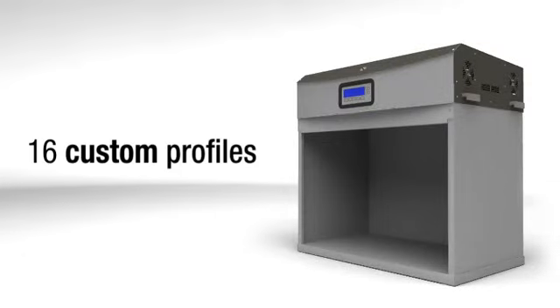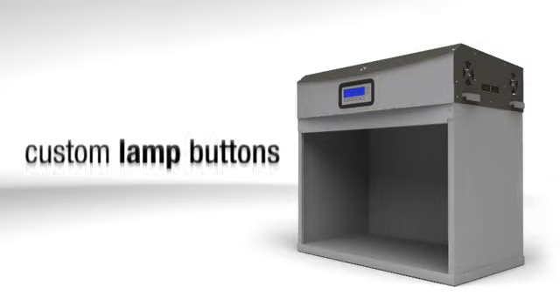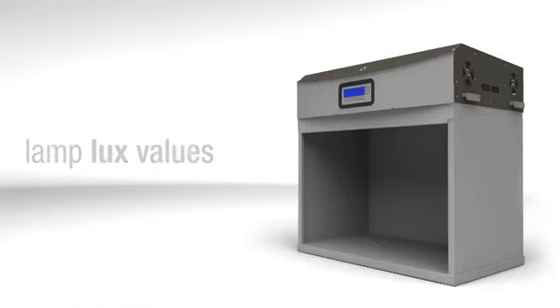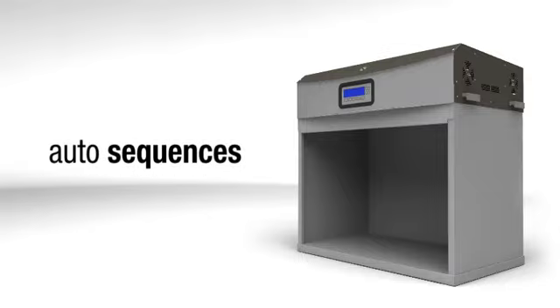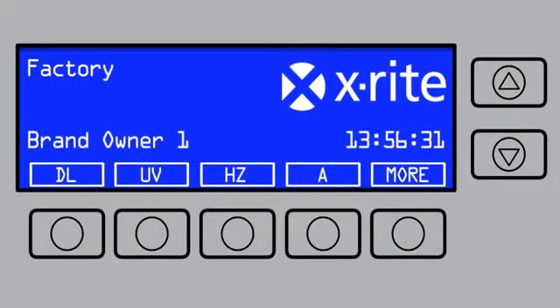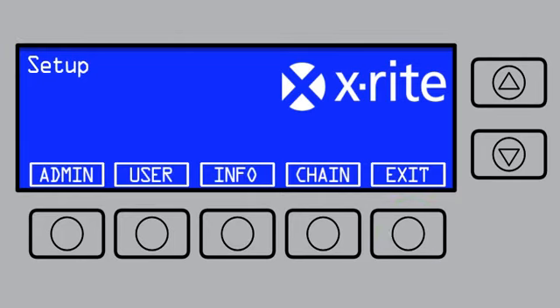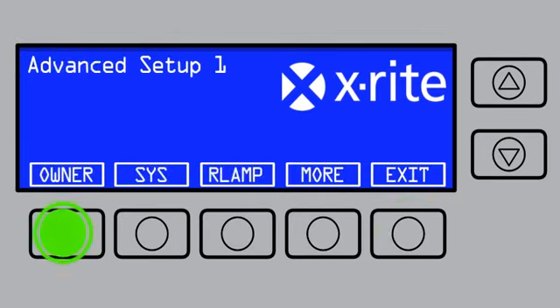The SpectraLight QC allows you to create up to 16 custom profiles with custom lamp buttons, lamp lux values, locations, and auto sequences. To create a custom profile, from the main menu, press and hold the More button until you see Setup. Press Admin to access the Advanced Setup 1 screen. Then press More to access the Advanced Setup 2 screen. Press Profile to get to the Profile List screen.